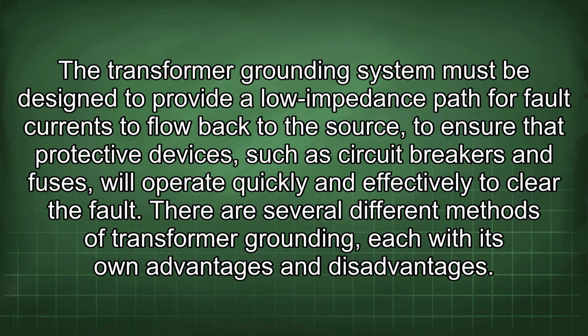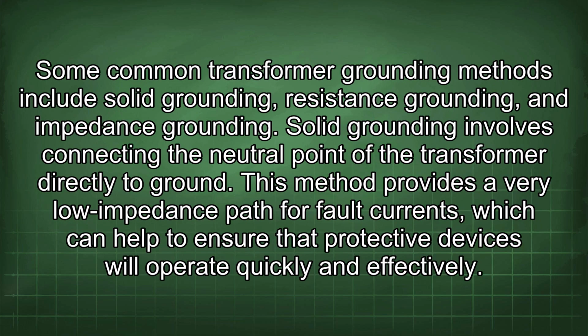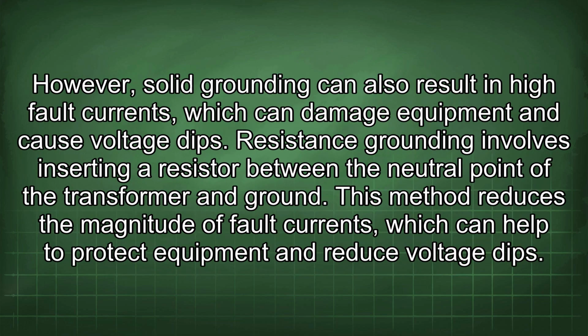There are several different methods of transformer grounding, each with its own advantages and disadvantages. Some common transformer grounding methods include solid grounding, resistance grounding, and impedance grounding. Solid grounding involves connecting the neutral point of the transformer directly to ground. This method provides a very low impedance path for fault currents, which can help to ensure that protective devices will operate quickly and effectively. However, solid grounding can also result in high fault currents, which can damage equipment and cause voltage dips.